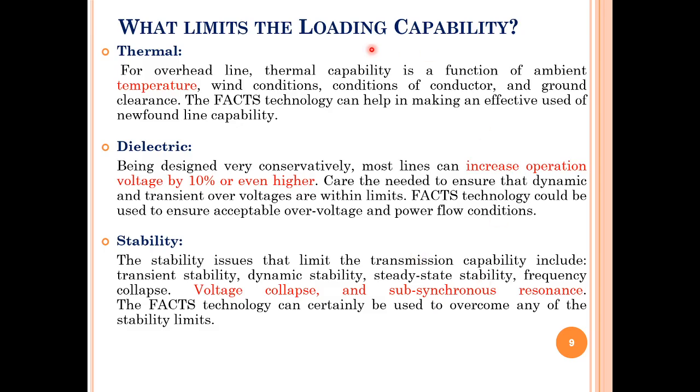Next. What limits the loading capability? Try to understand the meaning. Loading capability in the sense, for a particular thing, if I'd like to have some 10 megawatts of load, and beyond that I'd also like to use it, at that time so many limitations will be there. Those are three main points: thermal, dielectric, stability.